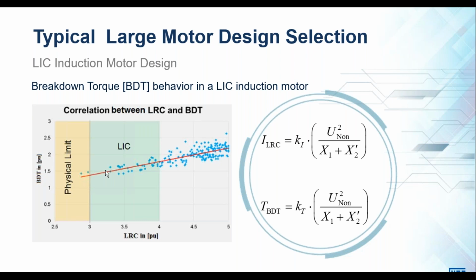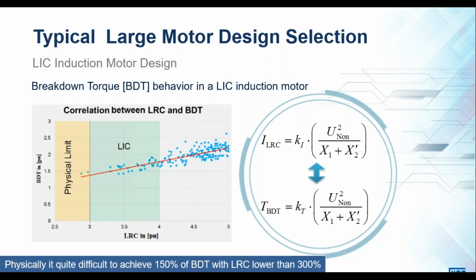What this means in practicality is that we get to some physical limit. In other words, it is impossible for us to drop a motor's locked rotor current or starting current below a certain value without starting to impede the breakdown torque. We found that physical limit to be close to the 3 times starting current condition. Physically quite difficult to achieve 150% of breakdown torque with locked rotor current lower than 300%.